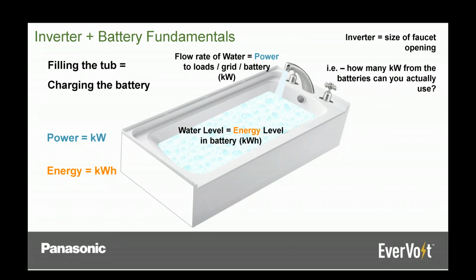So really, when you're looking at an energy storage system, you have two major components: the battery component and the inverter. Similar to solar, batteries store the power in DC, so we need the inverter to convert it to AC to use it in the home. So you have the balance between what the inverter can do, which in this example is the faucet, and then you have your tub, which is your tank of energy, your kilowatt hours. Pairing the right size battery to the inverter, and basing that off what the customer is actually going to use, is really the right way to go about designing a system.